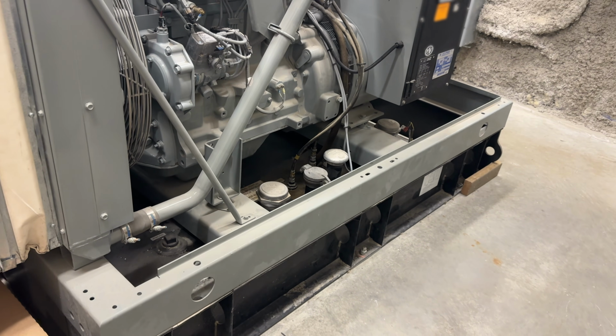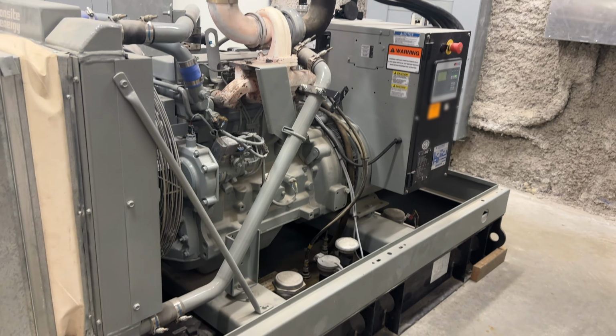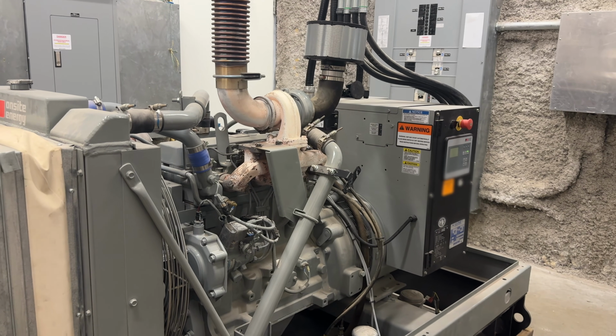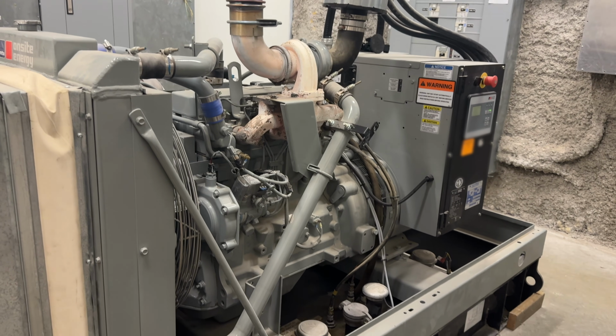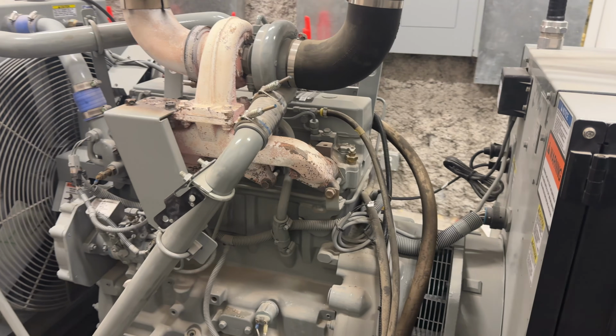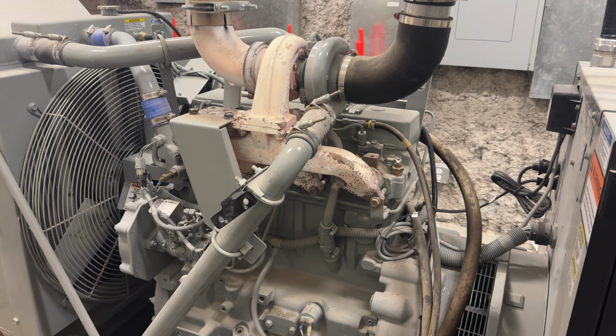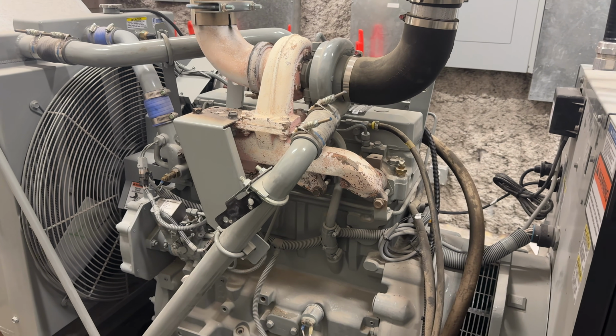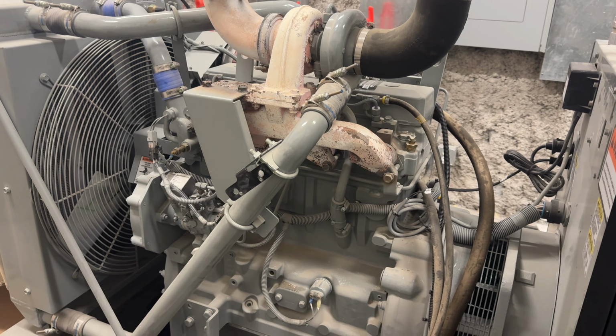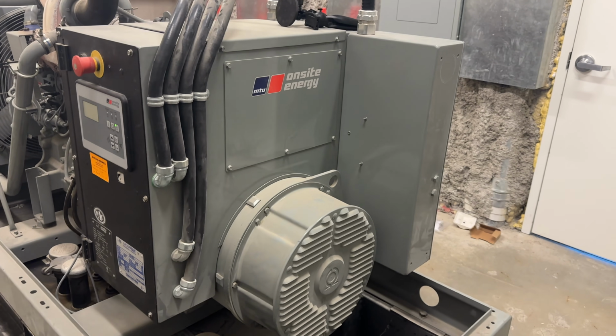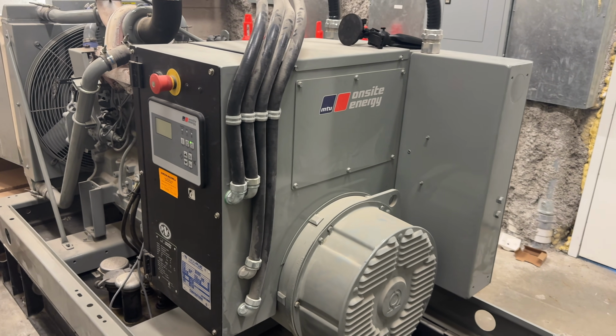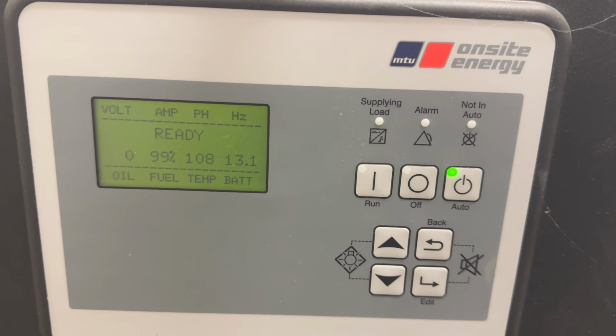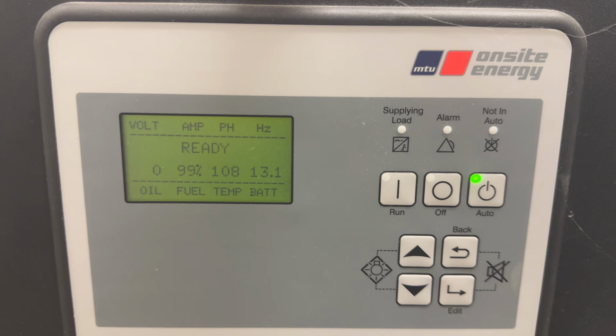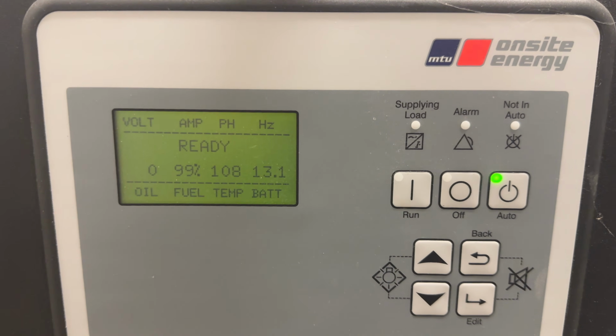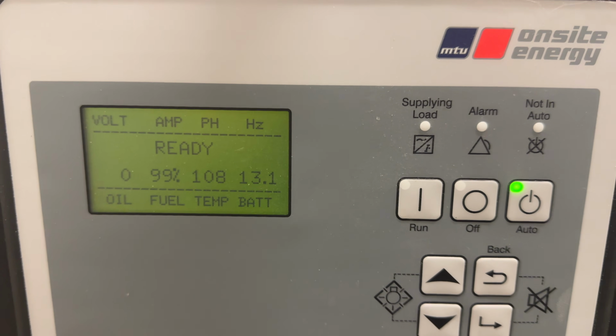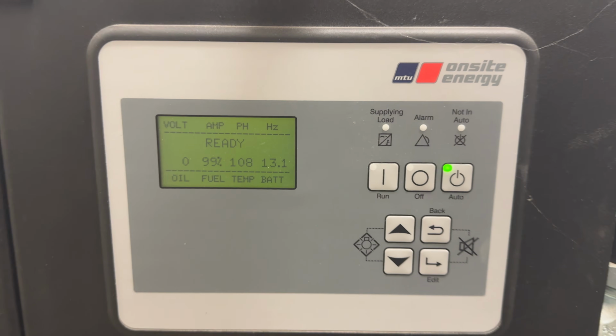I believe this would get around 30 hours of use if I was to calculate the time it gets from one tank, but that obviously can be refilled during the outage as well. This is powered by a 4-cylinder turbocharged diesel. This is a John Deere engine on this, and this has an MTU generator head and controller on it. It's an MTU generator. You can see it is in auto, as it should be. Fuel is right full. You can see that the block heater's working, keeping the temperature up, and battery voltage is fine. So there you go.